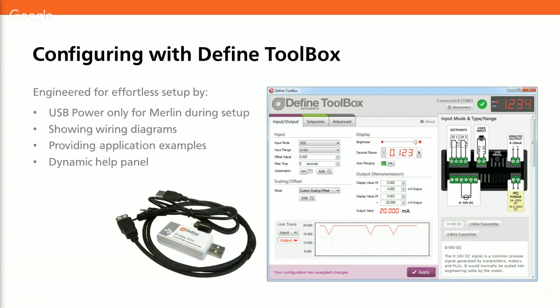Do keep in mind that when you are using the USB to power the Merlin, the majority of the functions will operate as normal, but the 4 to 20 milliamp output won't operate and the excitation won't be available for sensors. However, you can still configure the 4 to 20 milliamp output. The software allows you to enter all the parameters, and it gives you a simulated value for what the output would be if you had the power connected.